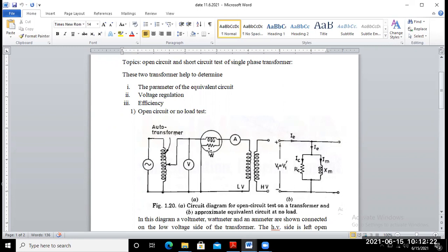So what are the components of the power losses at the no load condition? I have already said that one is the core loss, which is a very important loss, and some part is the ohmic loss, that means I square R loss. Since the no load current is small, the I square R no load loss is very small. What is the current required for no load condition? 2 to 6% of the rated current. Whatever the rated current of the transformer is, the no load current is that fraction of it.